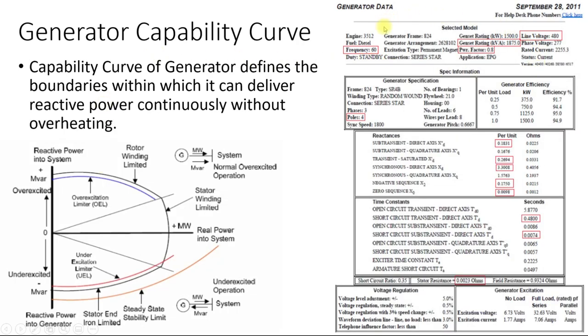Here is a typical generator data model. In this model you have the sub-transient reactance, the transient reactance, and the synchronous or direct axis reactance. For load flow analysis, you can use the direct axis reactance, whereas for short circuit analysis or transient stability analysis, you will require both the sub-transient reactance and the transient reactance along with their time constants. The additional data available includes the voltage, MVA, or KVA rating of the generator.